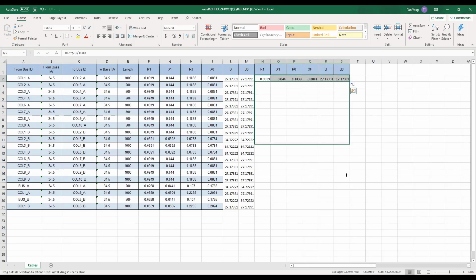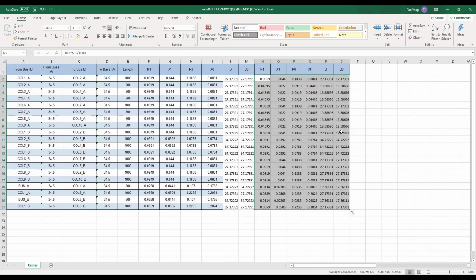Now the resistance would be equal to resistance times length divided by the length unit. It's 1,000 feet. I need to fix this cell as E2 because everyone would use it, so don't shift it. It's always E2. What's my charging? My charging would be the charging per 1,000 feet times length. I need to fix this as well, divided by 1,000, right? Same for my B0. Now that's the calculated impedance and charging for this circuit. Now we copy the equations down below. Okay, I got all my impedances.